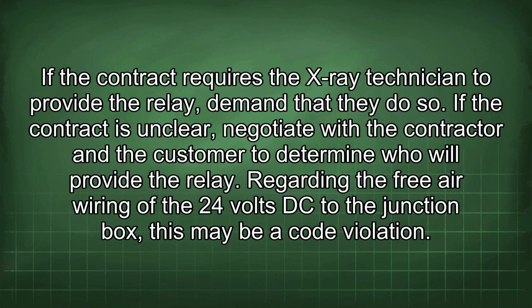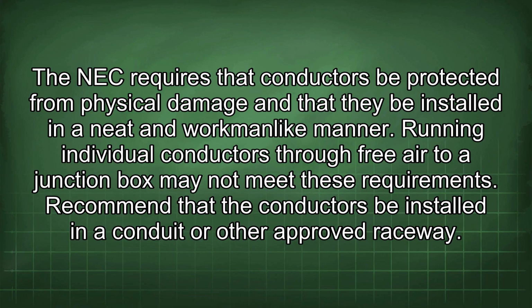Regarding the free air wiring of the 24 volts DC to the junction box, this may be a code violation. The NEC requires that conductors be protected from physical damage and that they be installed in a neat and workmanlike manner. Running individual conductors through free air to a junction box may not meet these requirements. Recommend that the conductors be installed in a conduit or other approved raceway.